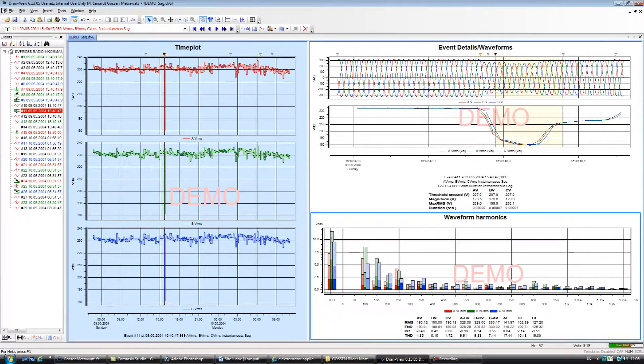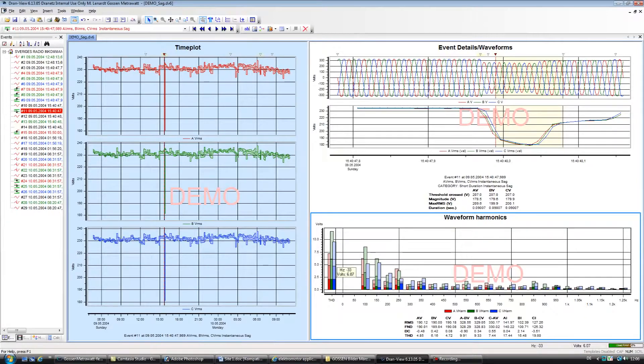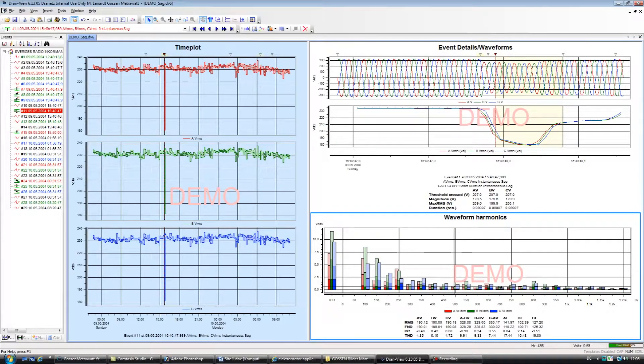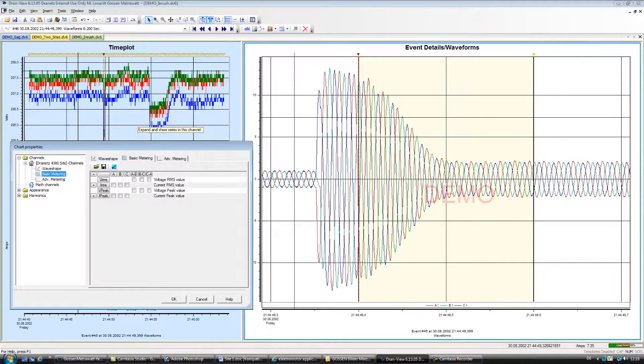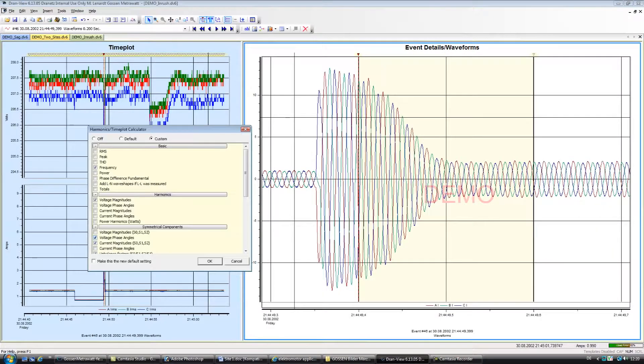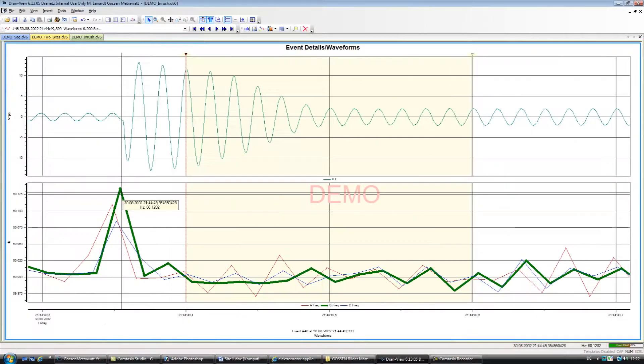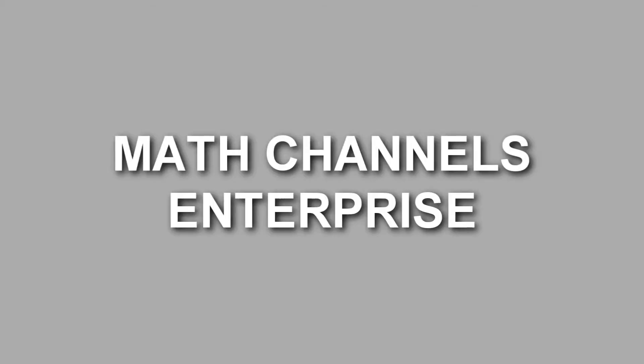including individual harmonics, VTHD, ITHD, VRMS, IRMS, frequency, and others. An example is generator testing, where it's common to require cycle-by-cycle frequency trends during generator startup.